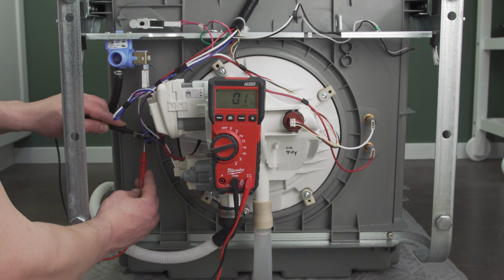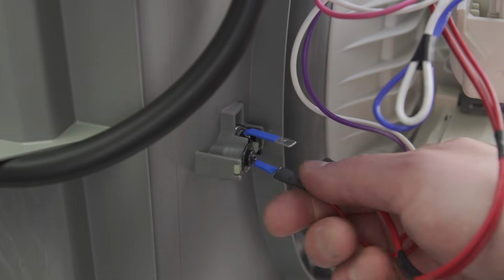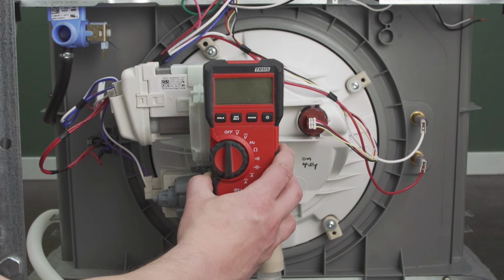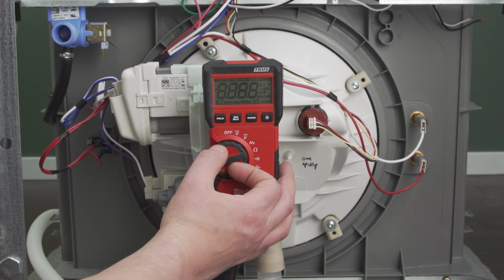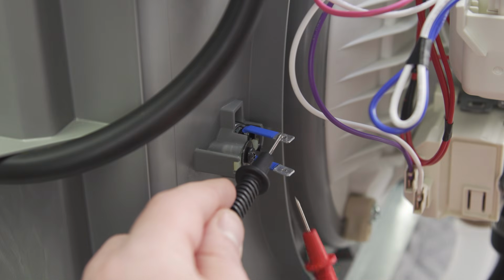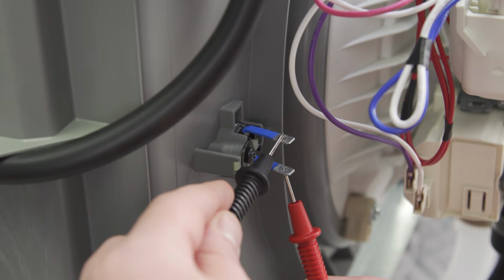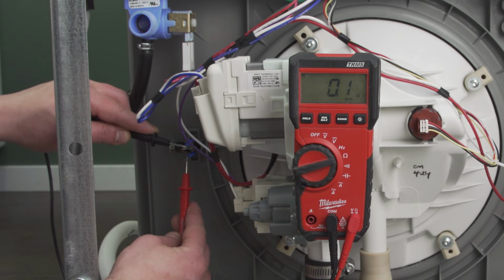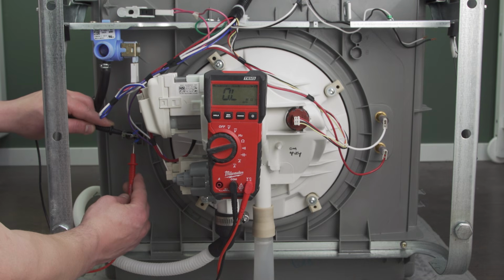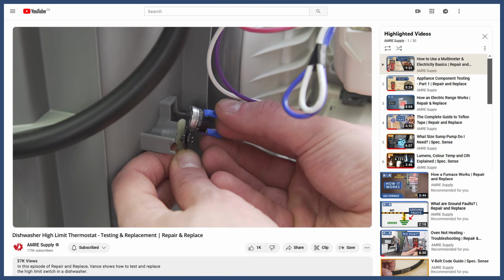The thermostat can be tested in place while it's still mounted. First, disconnect the wires. Set your multimeter to the resistance setting. Touch each probe to each terminal. There should be a resistance reading between 0 and 1 ohm. If there is no continuity, an infinite reading, or a resistance in the millions of ohms, then the thermostat has failed and will need to be replaced. You can see more in the video linked below.